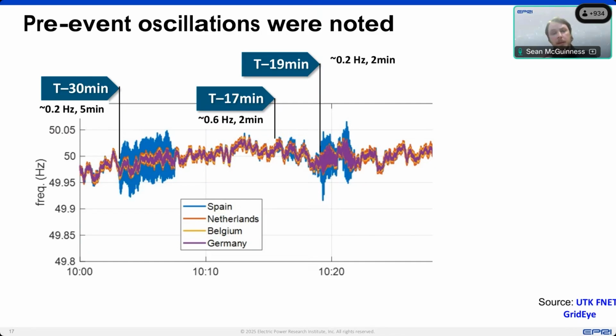Then at T-minus 19 minutes, we saw the 0.2 hertz oscillation restart again. It was a little bit larger in magnitude, but it did die out after about 2 minutes. And as you can see from this, there was a number of active oscillations. However, oscillations in themselves aren't enough to bring down a grid.